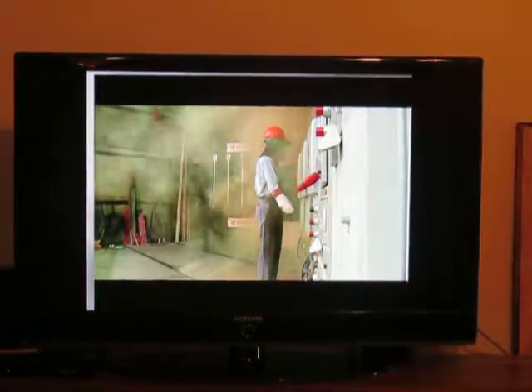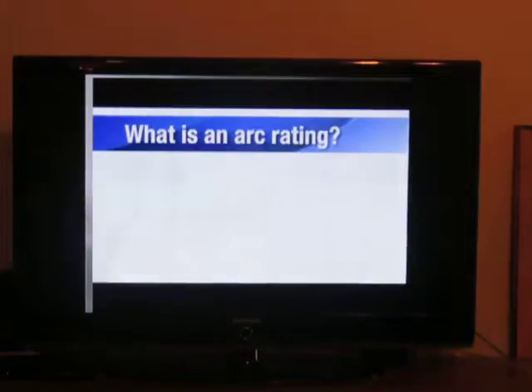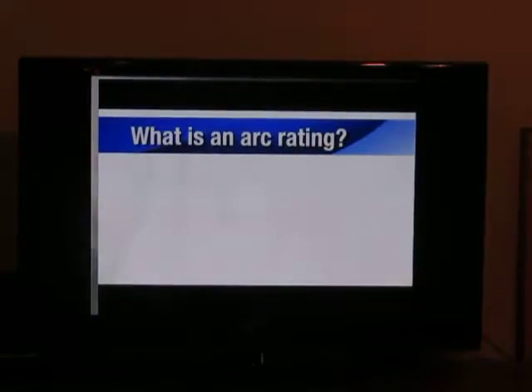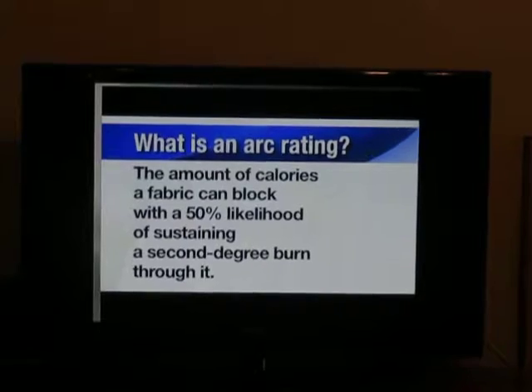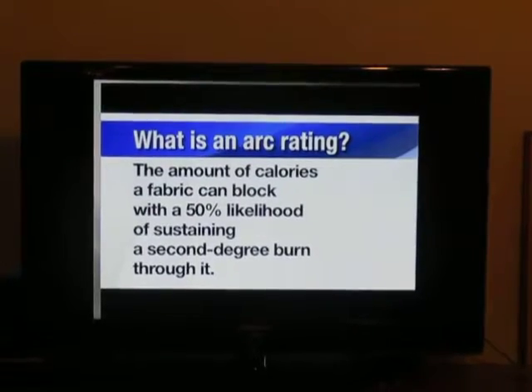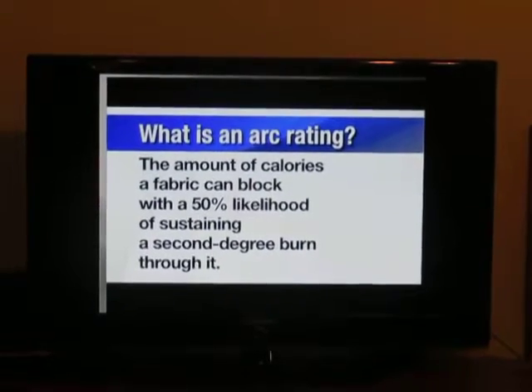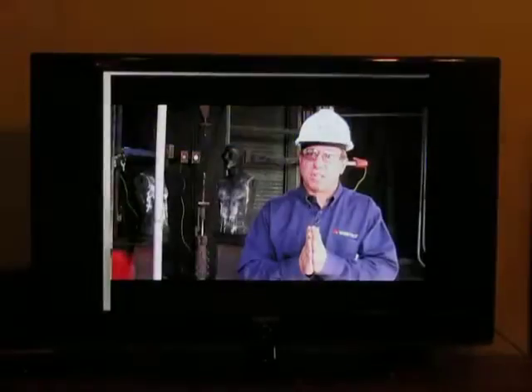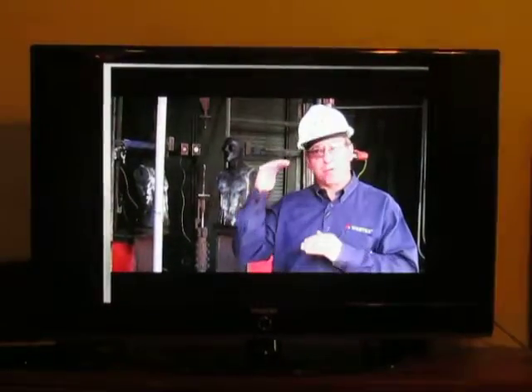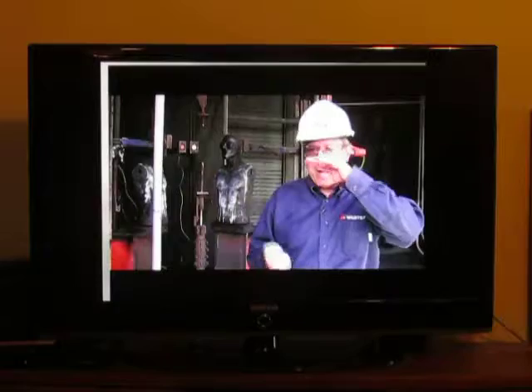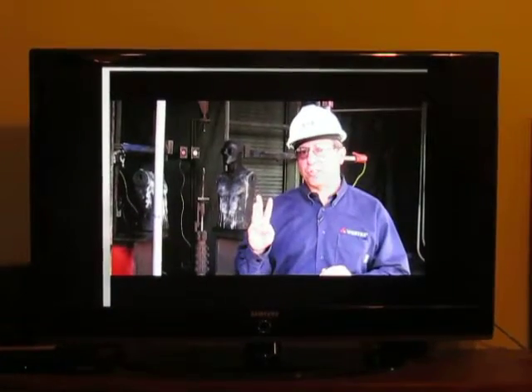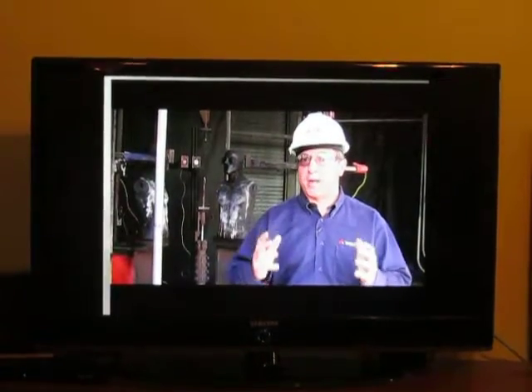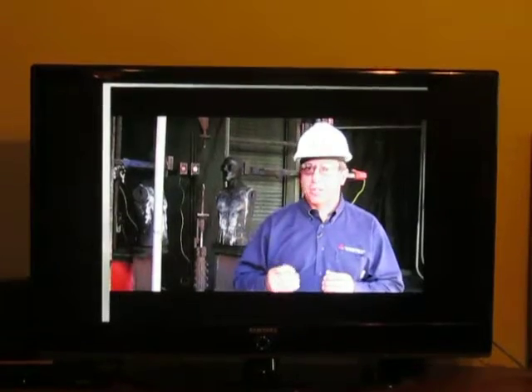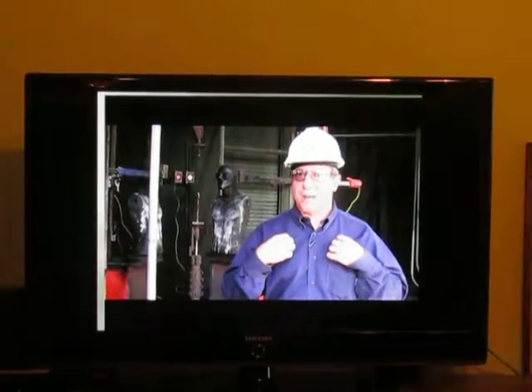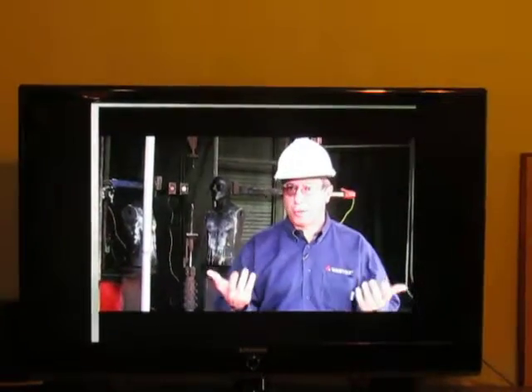Understanding how to protect yourself begins with understanding how arc flashes are measured. An arc rating is the amount of calories that a fabric can block with a 50% likelihood of sustaining a second-degree burn through it. So what an arc rating does is use the apparatus behind us, but with panels instead of mannequins, so that they're flat fabric panels. 3 panels in each arc, 7 arcs gives you 21 data points, and the computer then measures the 50% probability. In the case of this fabric, it's 8.7 calories, and that becomes your arc rating.